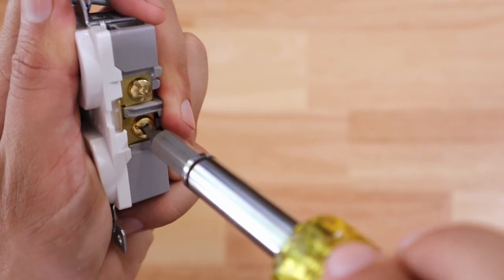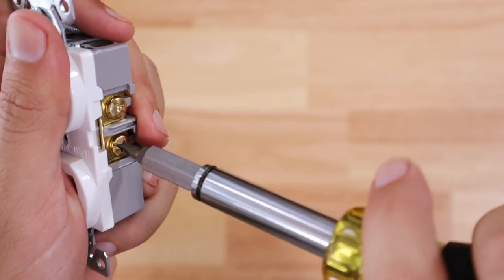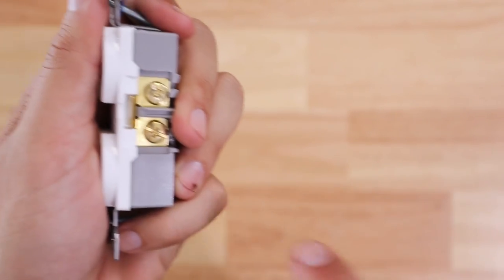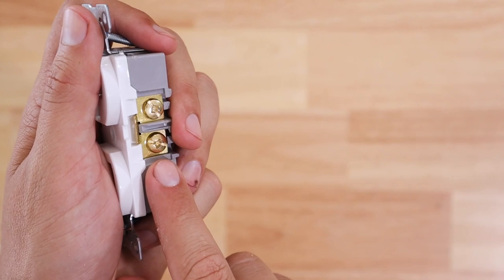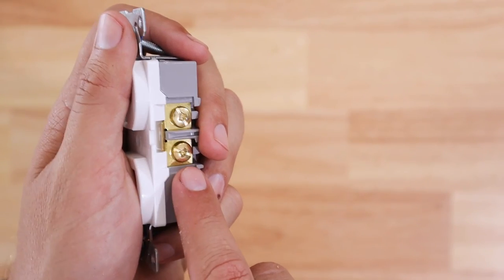Even though this is nice and tight, because of manufacturing of some of these terminal screws, they're not always built the best. When you go to really tighten down on it, I've found on certain receptacles and light switches, it can actually start to wallow out the very middle part of the head.